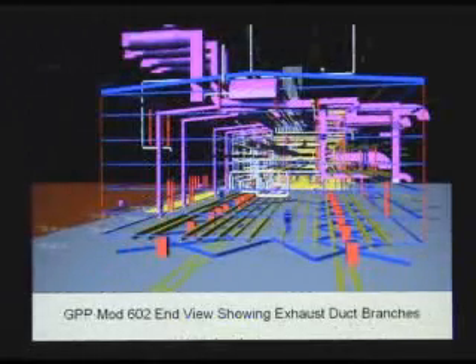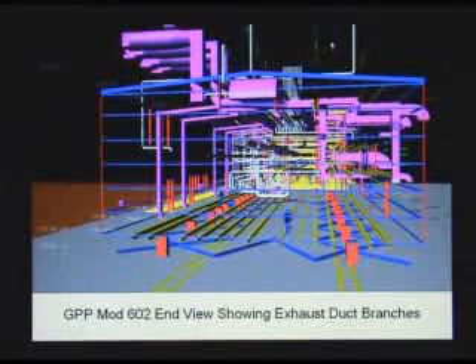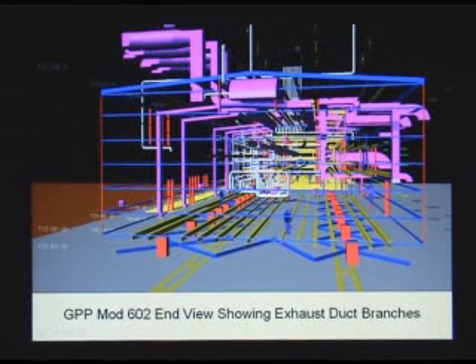This is another shot of that 602 view. You can see we have pretty much lots of ductwork. One of the reasons we have a lot of ductwork is that we want to remove all the hydrocarbon gases from the module. You've got a lot of methane, which is normally lighter than air. It accumulates on the top. And the propane, which is heavier than air, goes at the bottom. So we do have ductwork down below and on top.